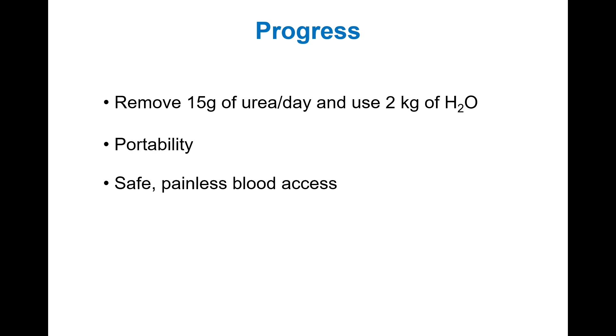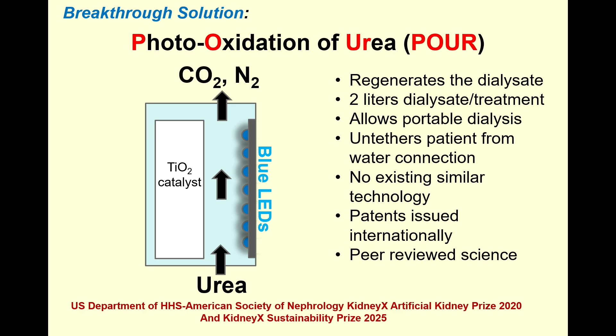One of the foundation technologies that we have developed that allows us to think about portability is what we call the photo-oxidation of urea. Photo means light. Oxidation means we're going to turn that urea into carbon dioxide and nitrogen, 2 inert gases that just go off into the air. So urea comes in, passes over a catalyst. It's exposed to blue LED lights, and that catalyst breaks it down to CO2 and N2. So suddenly, we no longer have to hook into a water hookup. The patient is untethered from the water connection. There's no existing similar technology that's available. This is the only one of its type for kidney dialysis. And we've patented it, and we've also published it in respected scientific journals. So the concept is out there, and the fact that it works is out there.